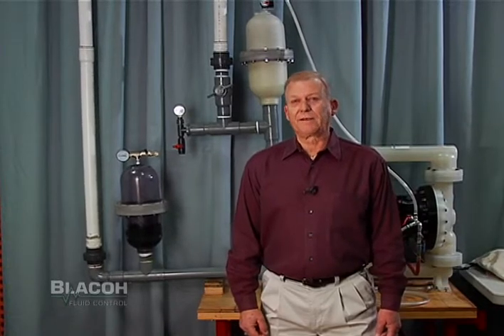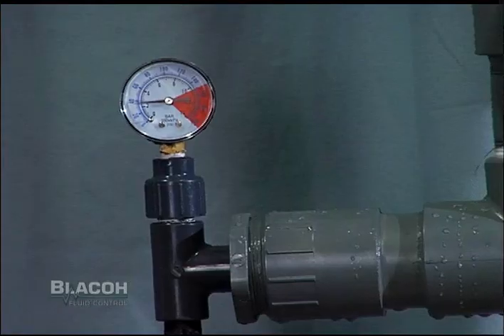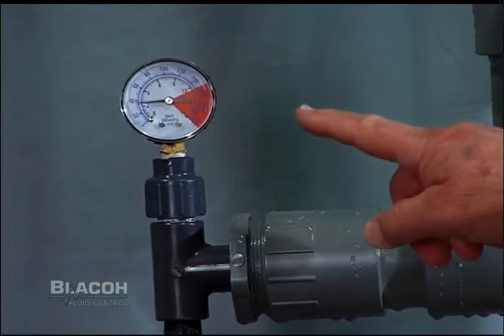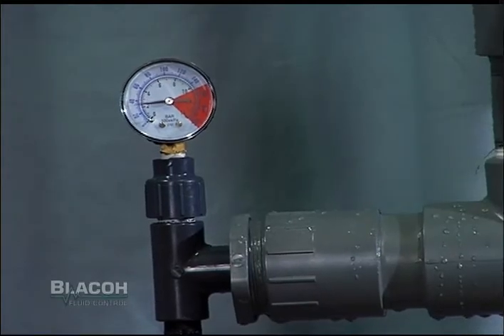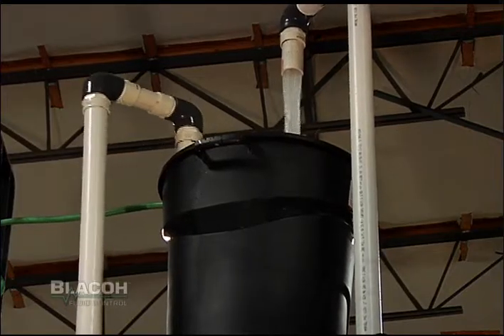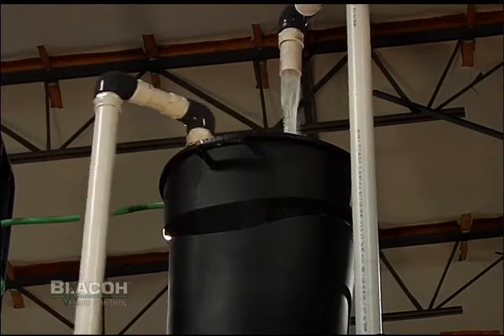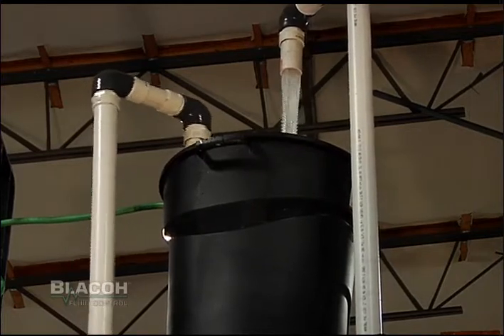The J model inlet stabilizer has been overcharged, so its bladder has been pushed down into the inlet and the stabilizer shut off. So in effect, it might as well not be in the system. The discharge dampener has already been recharged to the proper pressure charge. You can see that the discharge pipe is dampened, non-vibrating, and the discharge flow is continuous and non-pulsing. The discharge pressure gauge reads steady.